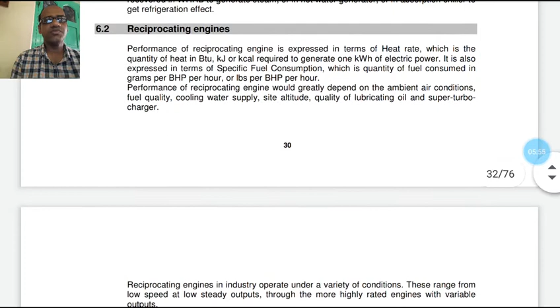Now, the performance of a reciprocating engine is expressed in terms of heat rate, which is the quantity of heat in British thermal unit, kilojoule or kilocalorie required to generate 1 kilowatt hour of electric power. It is also expressed in terms of specific fuel consumption, which is the quantity of fuel consumed in grams per bhp, that is brake horsepower per hour, or in lbs, that is pounds per bhp per hour. Performance of a reciprocating engine would greatly depend on the ambient air condition, fuel quality, cooling water supply, site altitude, quality of lubrication oil, and supercharger.